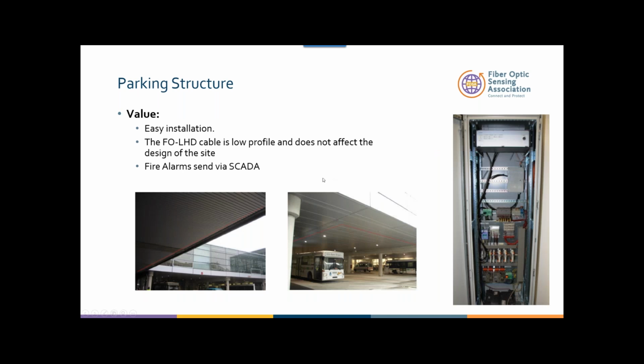We have parking structure as well. Here's an example of where you have the roof of a parking structure. The roof of the parking structure is ensuring that you can monitor the temperature at many locations. But most important, from a fire detection point of view, you don't need to bring physical point sensors. The point sensor heat detectors can be very costly in the sense that you have to wire each one of them and put them strategically in the right locations. With the fiber optic linear detection system, you can easily just run a cable, set up your zones virtually, and tie into the fire detection panel. On the right, you can see this is a fiber optic linear detection controller tied into the old fire detection panel as well.